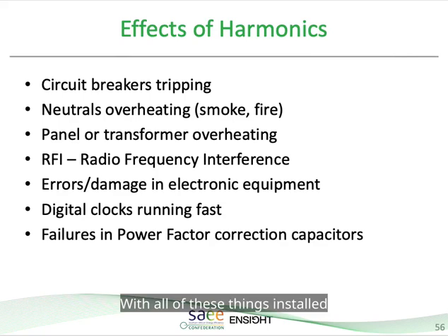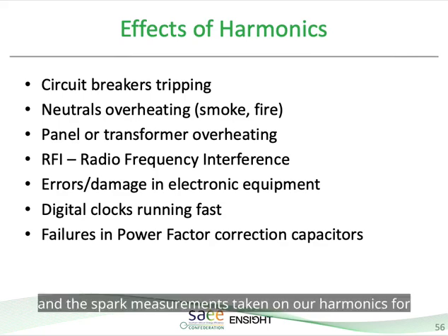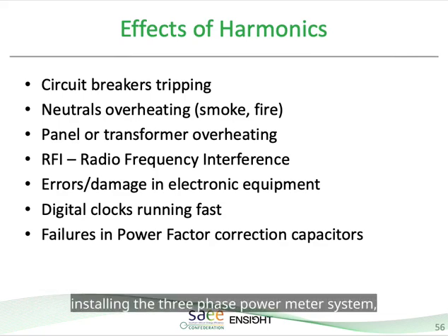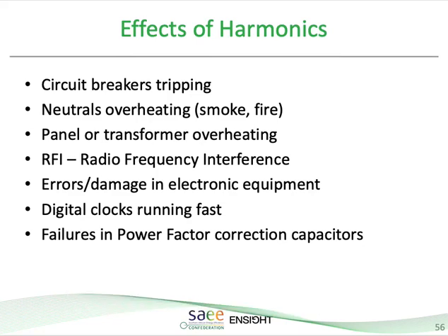With all the VSDs installed and the spot measurements taken on our harmonics whilst installing the three-phase power meter system, it was noted that the harmonics have issues, and this will be addressed further along the line.